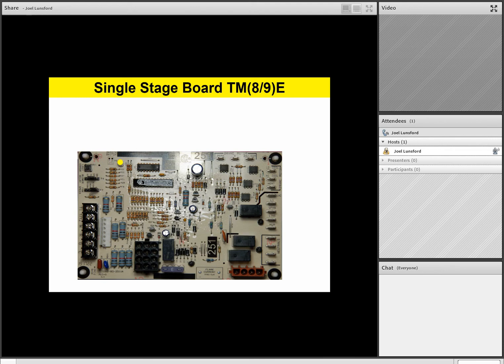And so in this first one we see that we have a continuous amber flash. So we have a yellow flash code on this board, and it's a continuous amber flash. Well, as we take a look at page number 21, we see a continuous amber flash indicates low flame current. And so we're going to check some of the following things. Number one is grounding. We mentioned this earlier, and we're going to stress it a little bit more right now. Grounding is the number one cause of low flame current. If you have poor grounding, you're not going to have proper flame current. So make sure that your grounding is very, very good from the furnace all the way back to the power panel. So check your grounding.